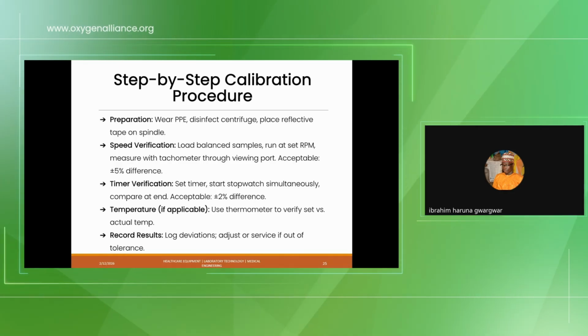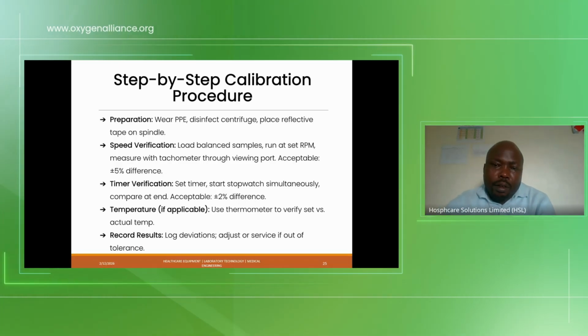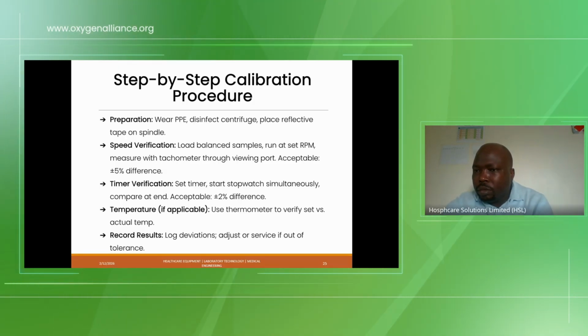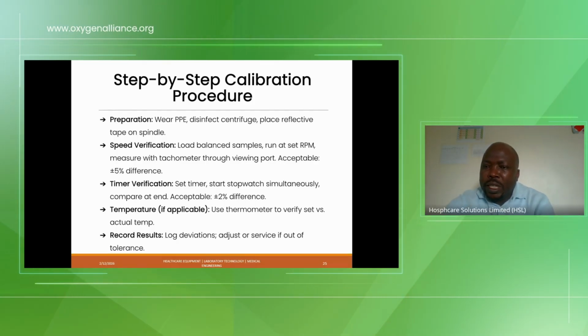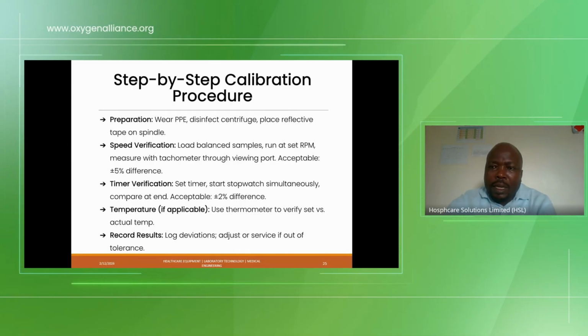Okay. So a tachometer, you use it for measuring motor speed, revolutions per minute. By using the digital tachometer, you need to put a reflective tape on the top of the revolving shaft. You need to set a common test speed, for instance, 1,000, 3,000, or 5,000. Then you run your test. By running the test, you will be noting them down, and then you compare with the data sheet from the machine, to see if the revolution matches the set revolutions per minute on the machine.